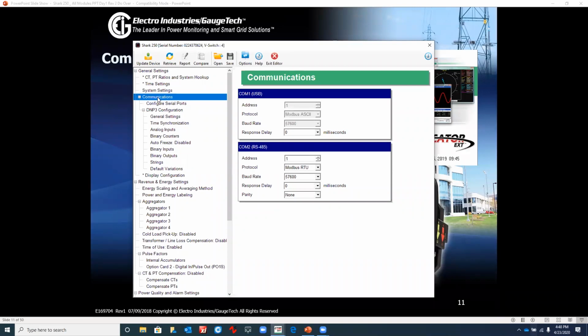You would need to connect at the protocol of Modbus ASCII and the baud rate of 57600. If you don't have that setting, you will not be able to connect to the meter using the USB connection. The 485 to the rear of the meter is a Modbus RTU protocol, and the baud rate again is 57600. So when you set up your connection, you would set it at Modbus RTU and 57600.